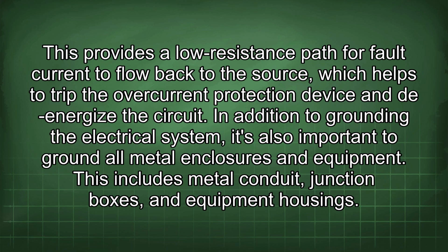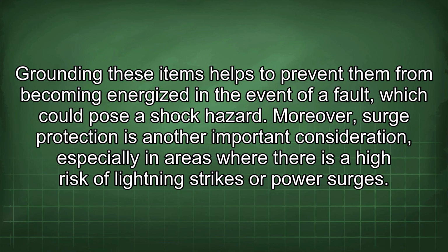In addition to grounding the electrical system, it's also important to ground all metal enclosures and equipment. This includes metal conduit, junction boxes, and equipment housings. Grounding these items helps to prevent them from becoming energized in the event of a fault, which could pose a shock hazard. Moreover, surge protection is another important consideration, especially in areas where there is a high risk of lightning strikes or power surges.